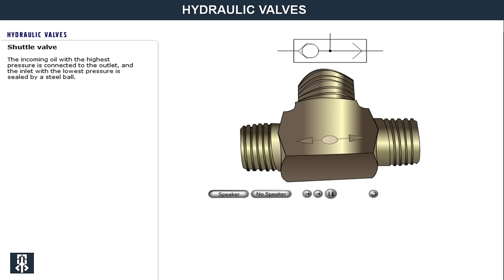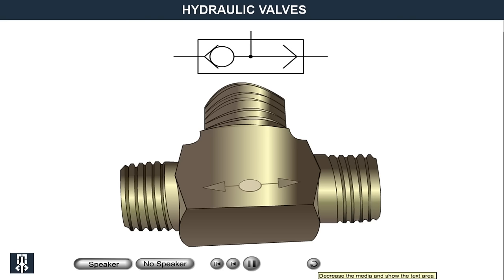The shuttle valve has connections to several inlets but only one outlet. The incoming oil with the highest pressure is connected to the outlet, and the inlet with the lowest pressure is closed by a sealing steel ball. A shuttle valve is used where several different signals can activate one and the same function, or if prioritising of different pressures is necessary.